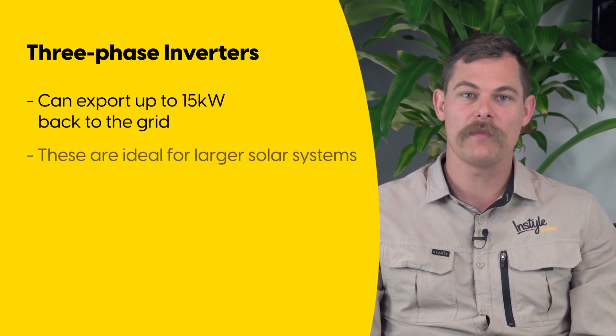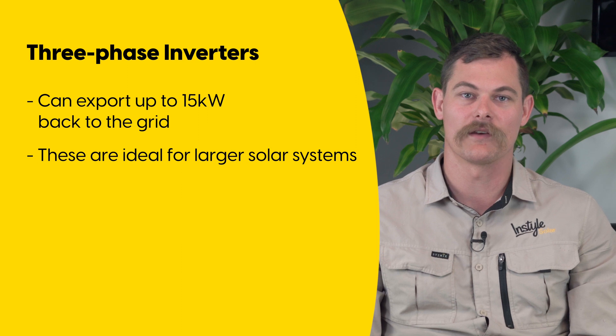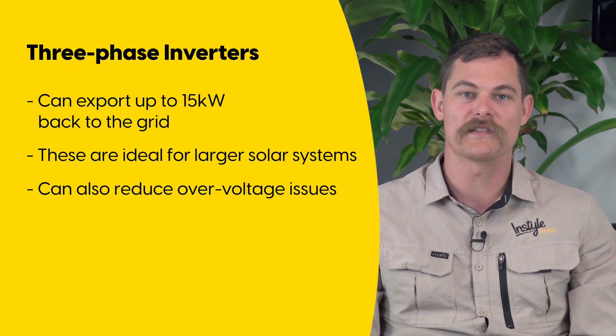If you have a large system and you want to take advantage of the potential savings, it makes sense to have a three phase inverter to work with your three phase connection. Three phase inverters can also reduce over voltage issues. Over voltage occurs when the voltage increases to levels that can potentially damage the grid or devices connected to it. Since three phase inverters have three cables to send back energy to the grid, the load can be shared and this reduces the risk of an over voltage occurring.